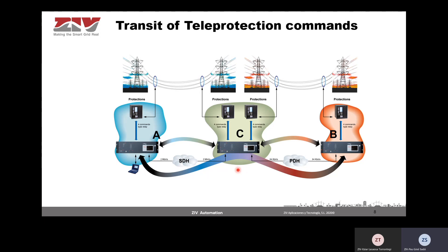The next example is similar to the first one, but uses one of the outstanding features of the teleprotection: the possibility of doing transits. In this example, substation C in the middle is equipped with two communication interfaces that allow the teleprotection to receive commands from substation A and transit them towards substation B, linking substation A to substation B through substation C. At the same time, substation C can also operate with substation A and from C to substation B. This is very common for T-line configurations.